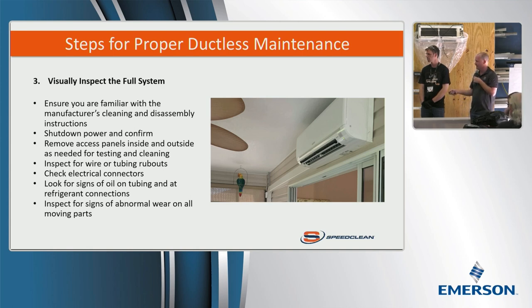Also check electrical connections, and the biggest thing I suggest is looking for signs of oil. If you see any signs of oil on your flares, especially on ductless systems, since flares are the number one leak point, take it seriously. I don't care if you put bubbles on it and don't see bubbles, because you can get really small microbubbles. You want to get it on there nice and still and watch it, but I'd suggest getting your electronic leak detector out at that point.